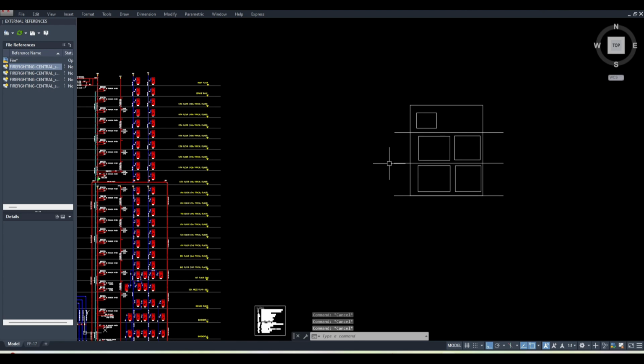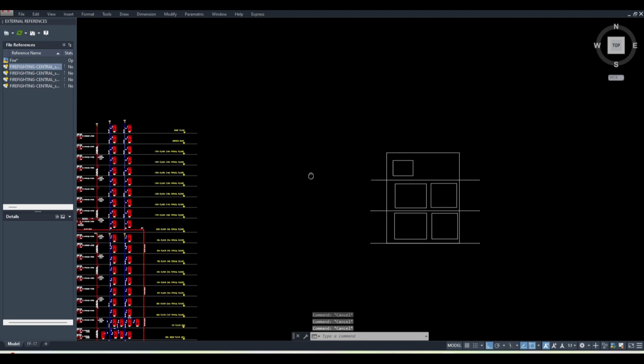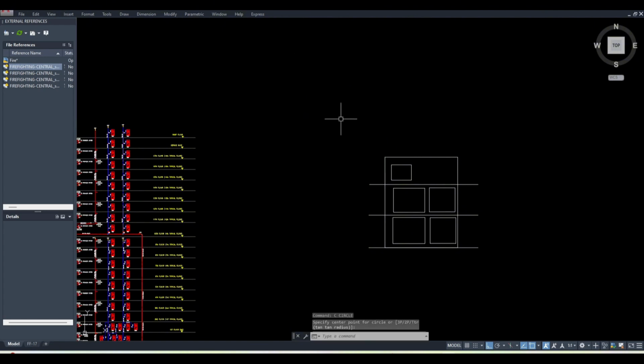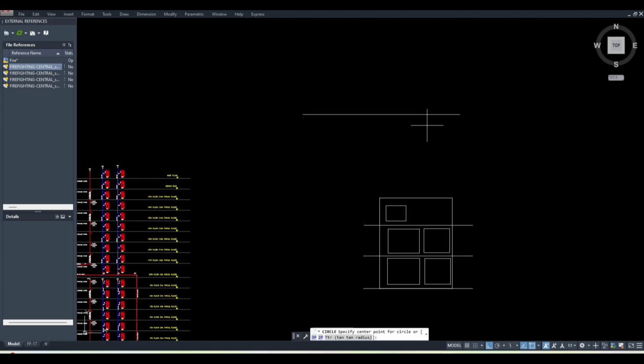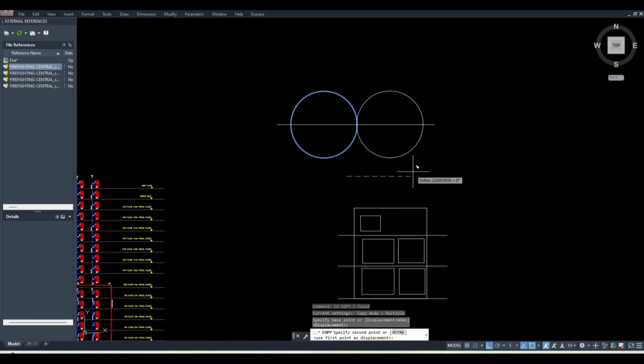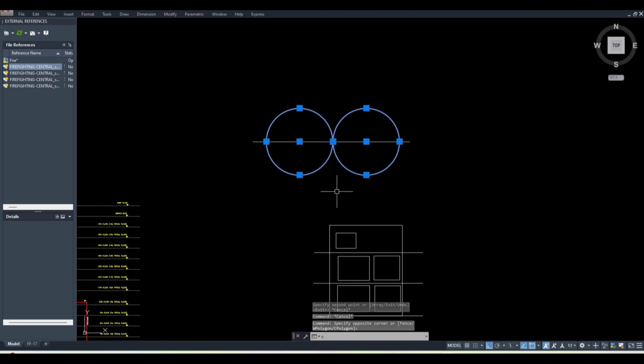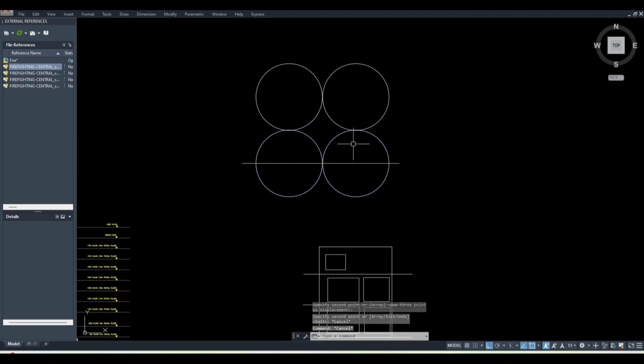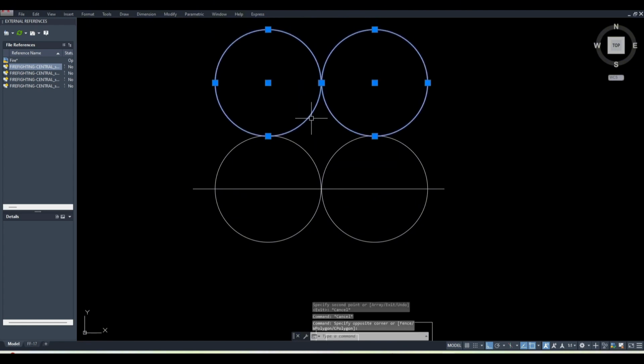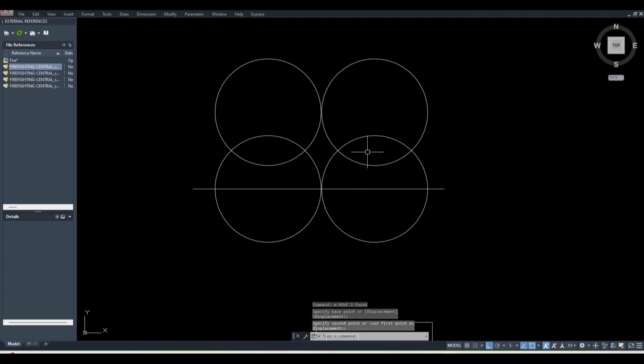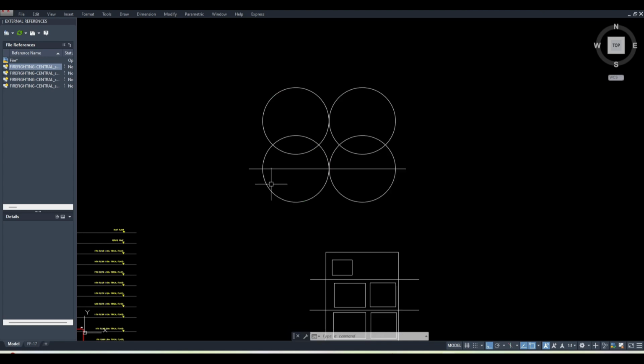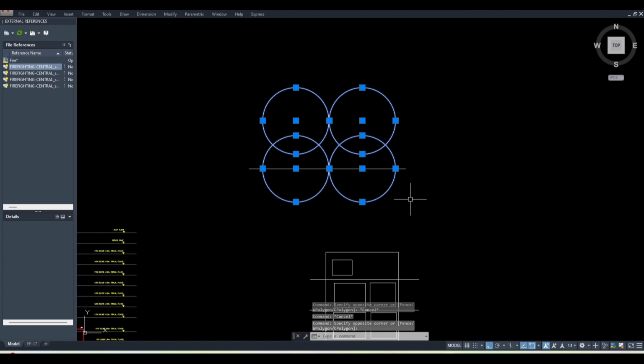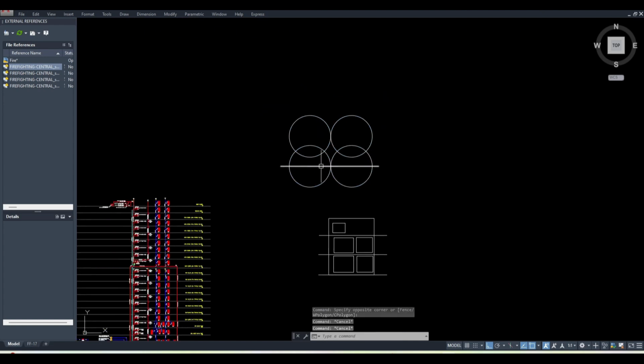This is a basic calculation we can do, but in actual practice some overlapping also happens. When we are arranging the sprinklers in a line, let's say here we are putting one sprinkler and then after that this one, so there is a gap created in between. One sprinkler should cover 12 meter square, but in between this dead zone should not occur. So we arrange it in such a way that these zones are minimized. To cover 12 meter square, normally a 4 by 3 arrangement is the best. 4 by 3 means the distance between sprinkler to sprinkler is 4 meter this side and 3 meter this side, or if 3 meter this side then 4 meter this side. So a 4 by 3 meter arrangement is the most suitable arrangement.